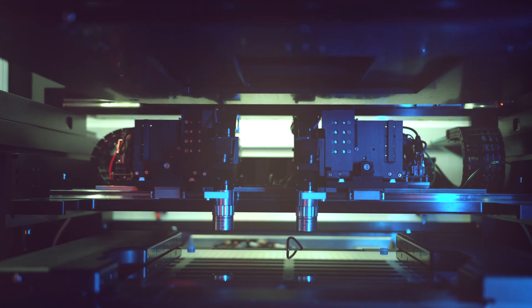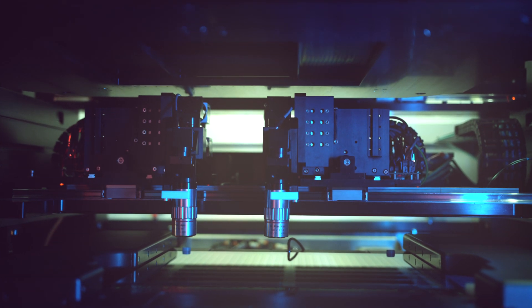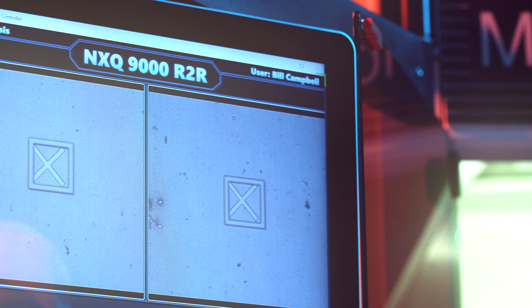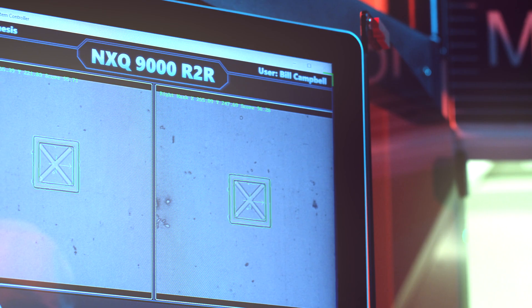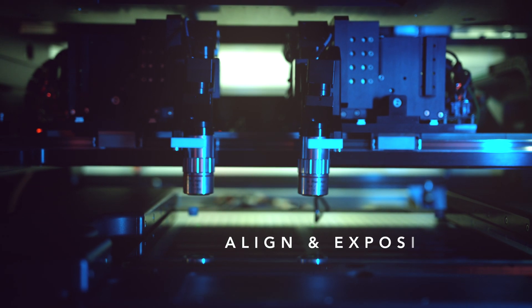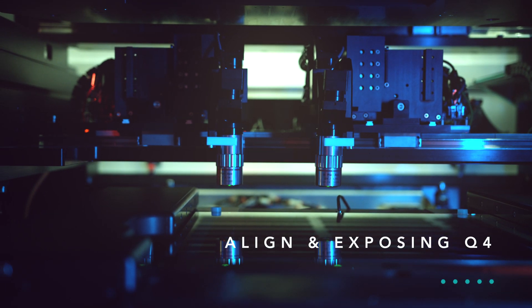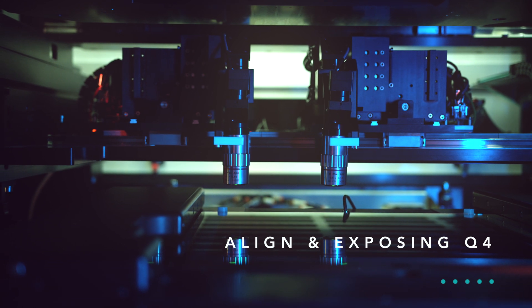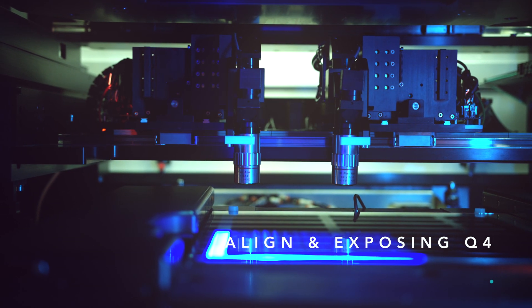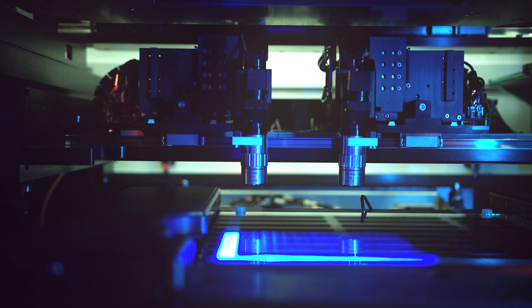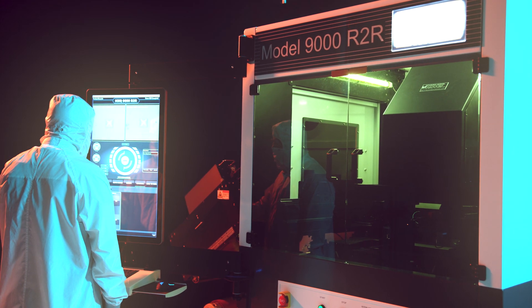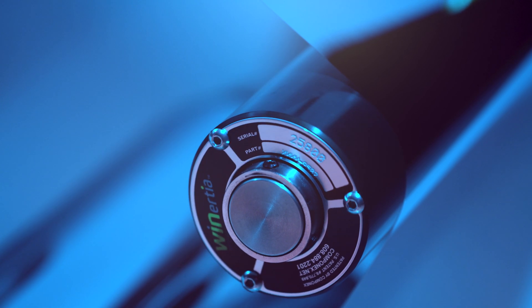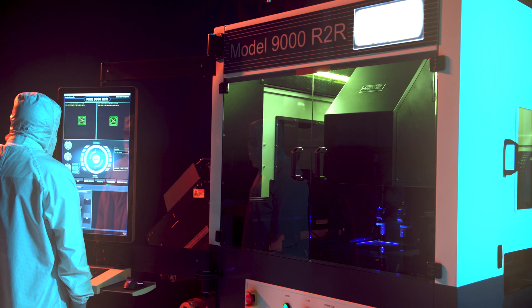In step and repeat mode, each field is aligned prior to exposure, with the exposure area optimized for specific process requirements, taking into account the required CD, overlay accuracy and throughput. The step and repeat mode assists in controlling run out and CD variations that are common problems with 1X large area mask aligners and full field projection systems.